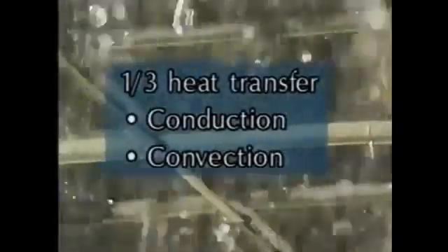In a cooling tower, heat that was in the water leaves the tower in the vapor as the water evaporates. Conduction and convection also play a role in a cooling tower. In the tower, water comes into direct contact with the air. When this occurs, some of the heat in the water is transferred to the air by conduction and convection. As much as one-third of the heat that's transferred in a cooling tower may be a direct result of conduction and convection heat transfer.